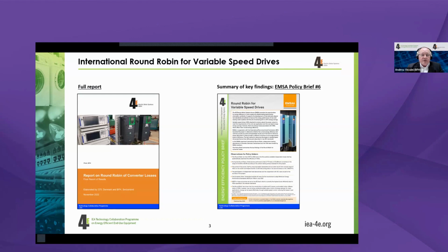One of the recent outputs where I was involved was the report on round robin on converter losses, where we work heavily with the International Electrotechnical Commission, the IEC, on the testing methods for testing inverters. Together with Sandy Nielsen from the Danish Technology Institute, we had a round robin for inverters and verified basically the performance of the market surveillance and performance of inverters from 0.12 kilowatt up to 75 kilowatts. This has also been published as a summary, as an EMSA policy brief, which can be downloaded on the website of EMSA.